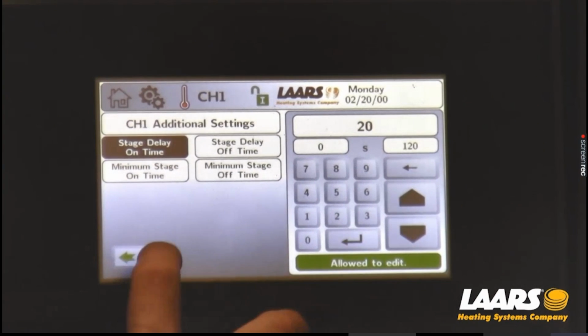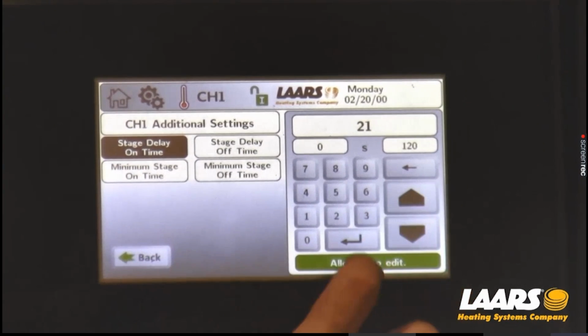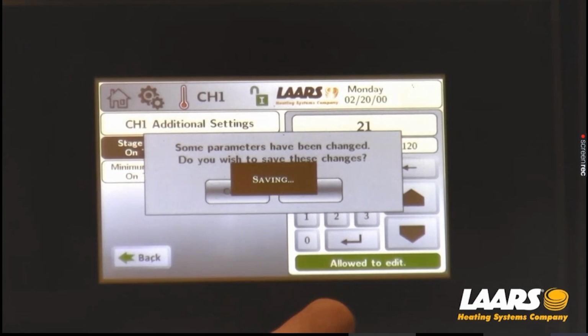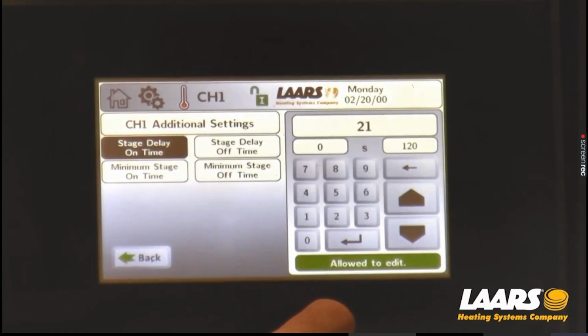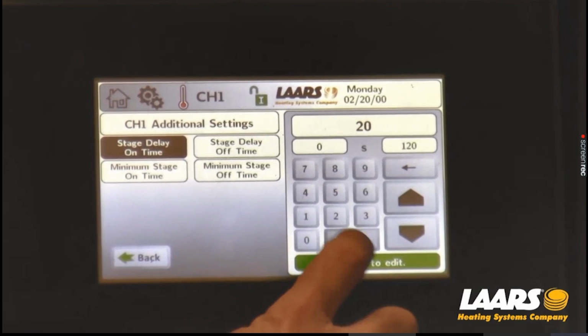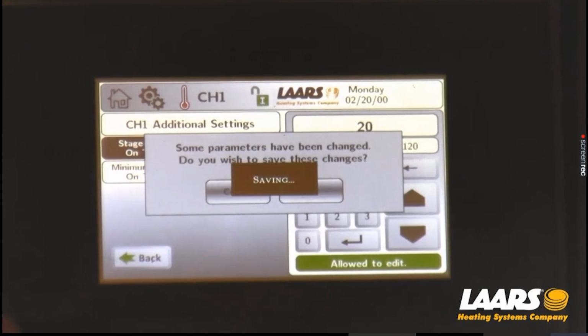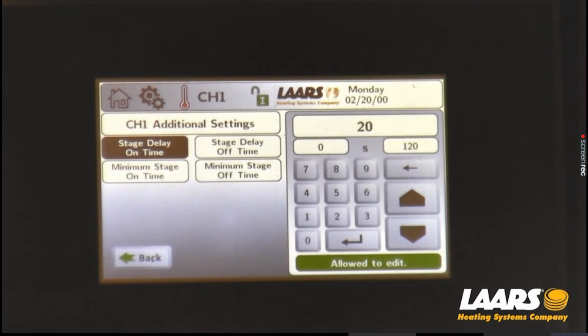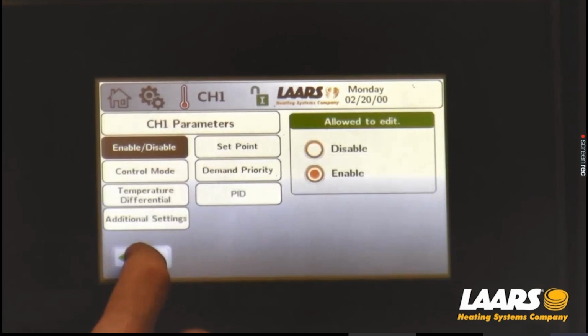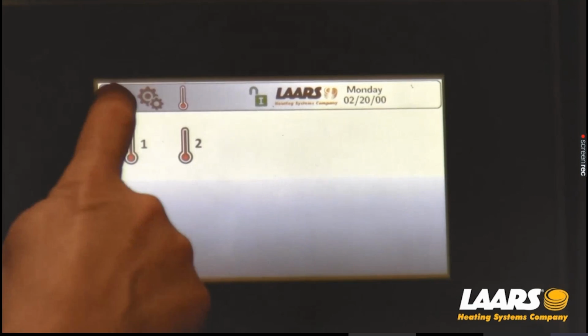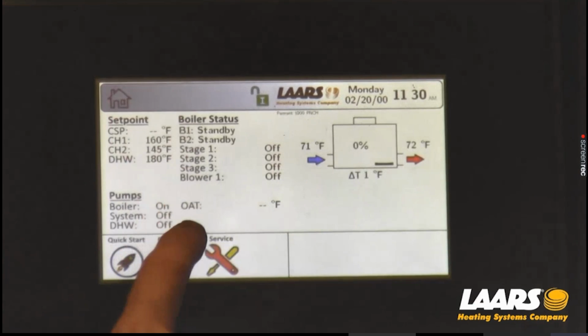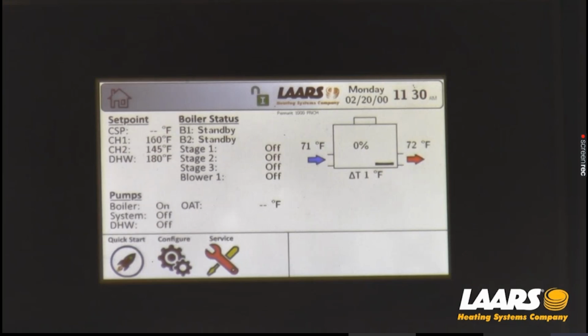Click enter, it's going to allow it. Again, if I had it here at 1 to 21, if I click enter, click OK, I'm going to go back in again and drop this back to 20. Click OK. And now my stage on delay time will come on in 20 seconds, every 20 seconds once we fire. I can go back to my home screen and now we'll watch the firing. I'm going to give this a call for heat.